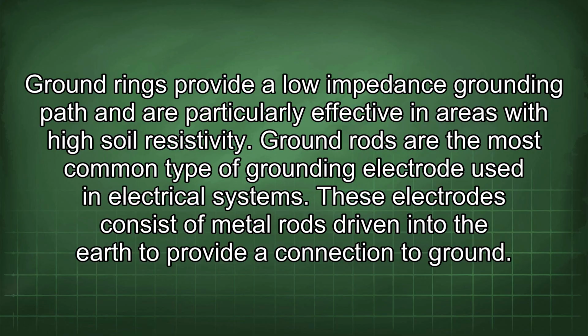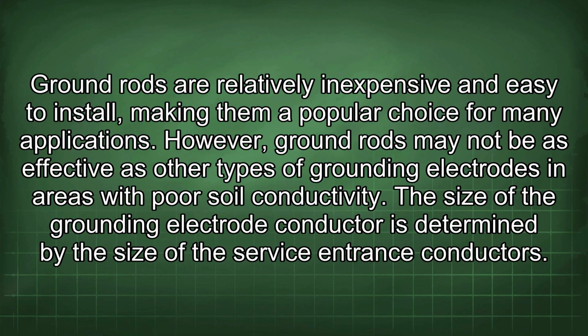Ground rods are the most common type of grounding electrode used in electrical systems. These electrodes consist of metal rods driven into the earth to provide a connection to ground. Ground rods are relatively inexpensive and easy to install, making them a popular choice for many applications. However, ground rods may not be as effective as other types of grounding electrodes in areas with poor soil conductivity.